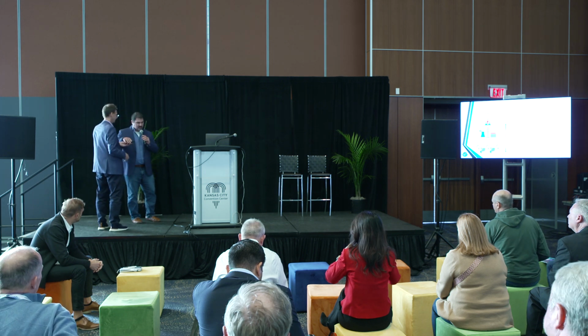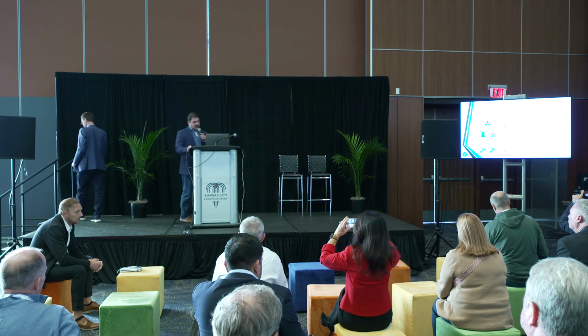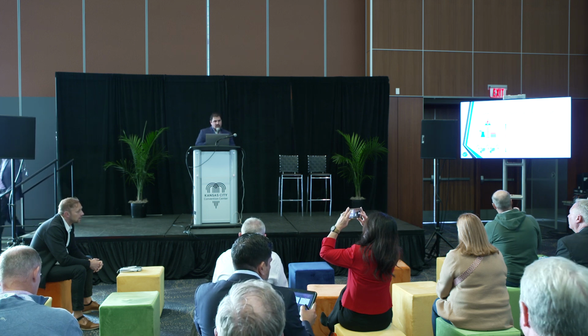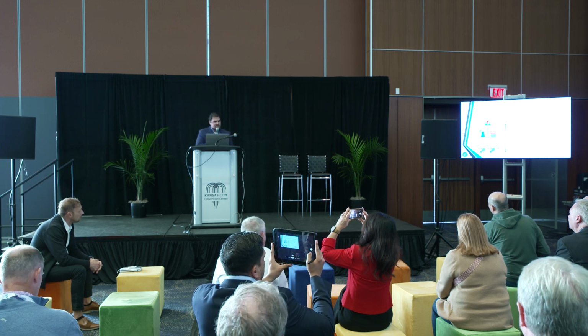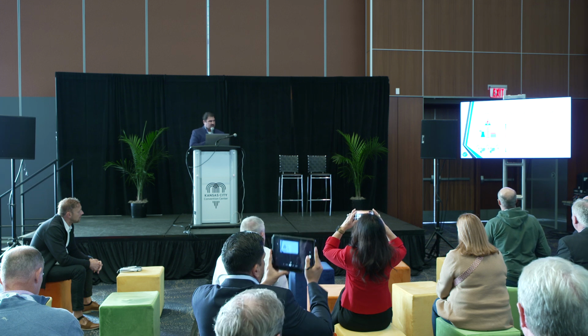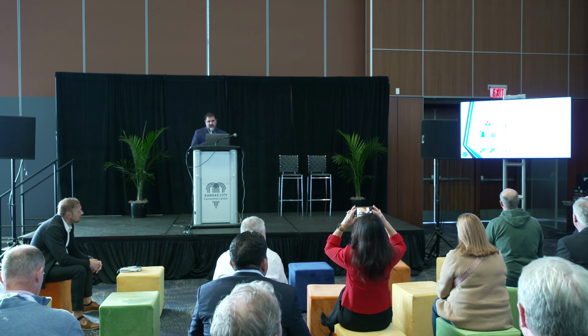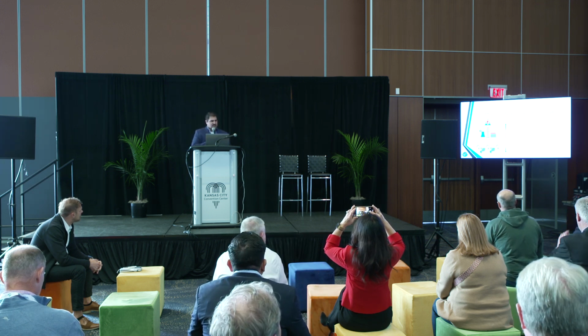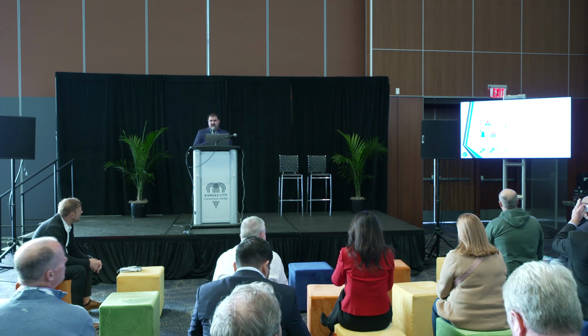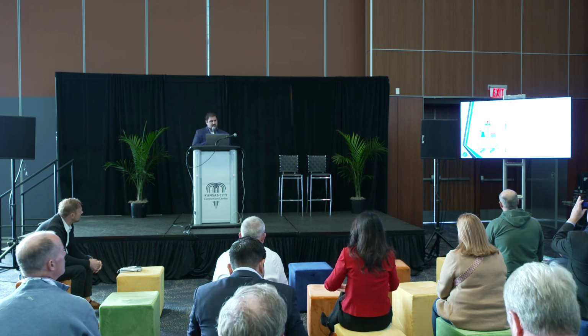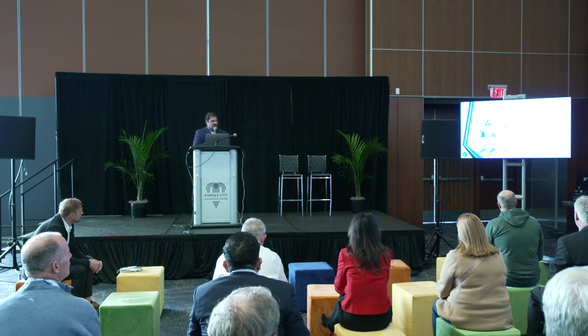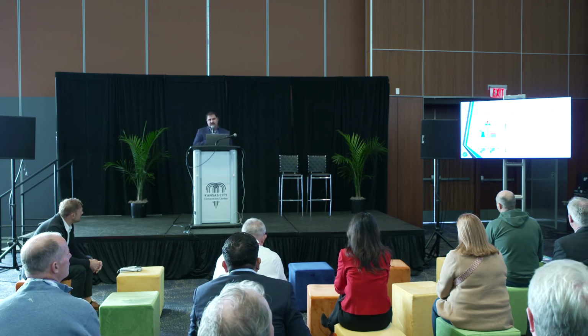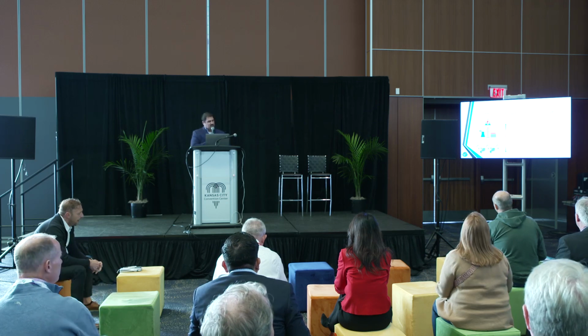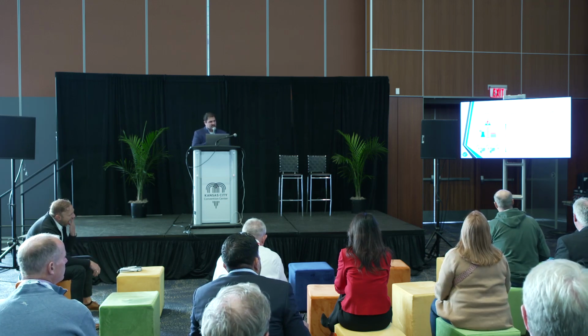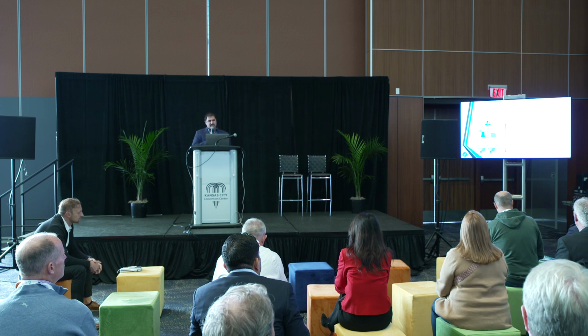Thank you, Jan. The core difference between AMI 1.0 and AMI 2.0, if you look at this diagram—it's quite simple from a picture perspective—is that we're taking distribution level asset telemetry and pushing it down to the edge of the network, to the consumers effectively. Reporting by exception, fine resolution data, and automation has foundationally been in our power plants, transmission systems, substations, and distribution for decades.